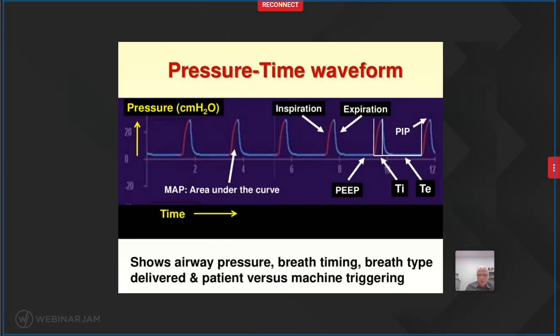So the pressure time waveform is not, in my criteria, the most important one, that is not the most useful one. It shows airway pressure, it shows breath timing, breath type delivered, and patient versus machine trigger.